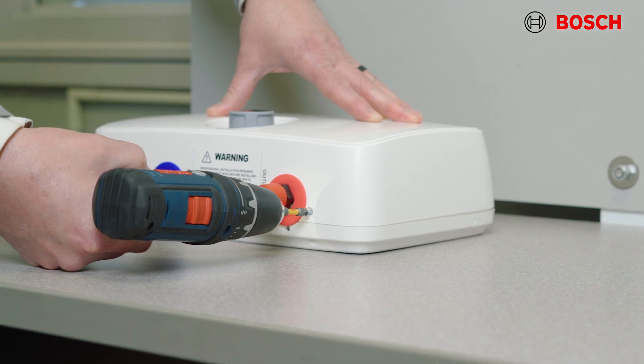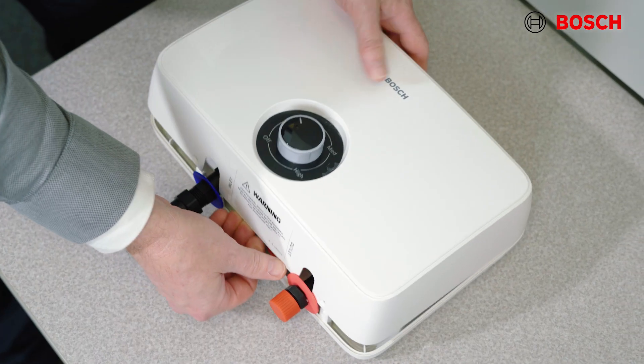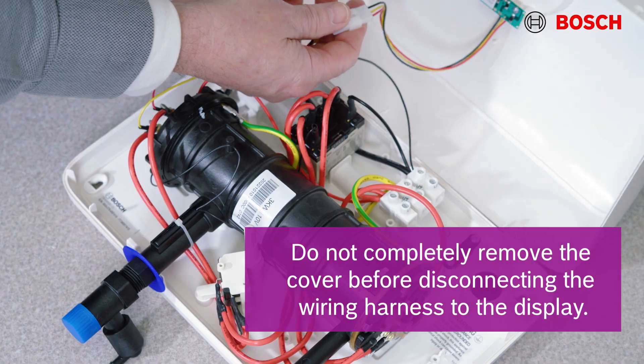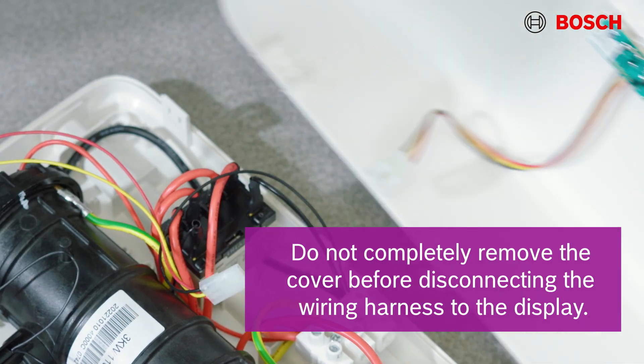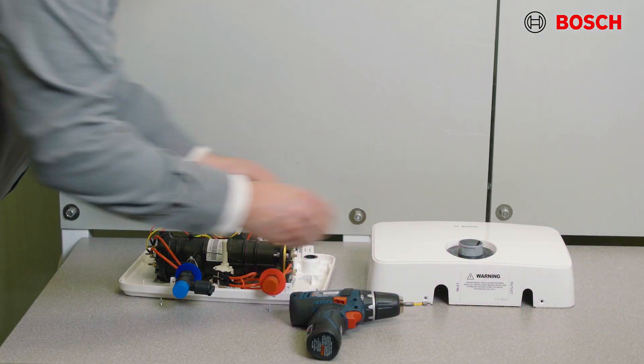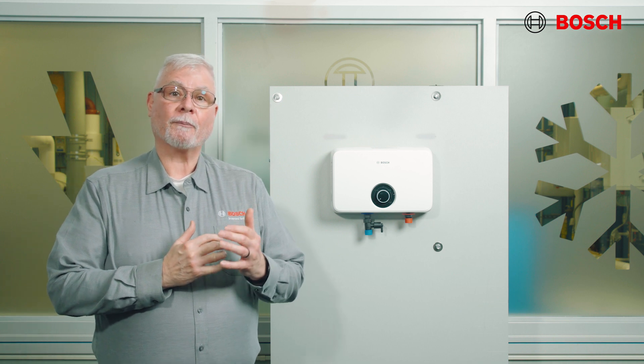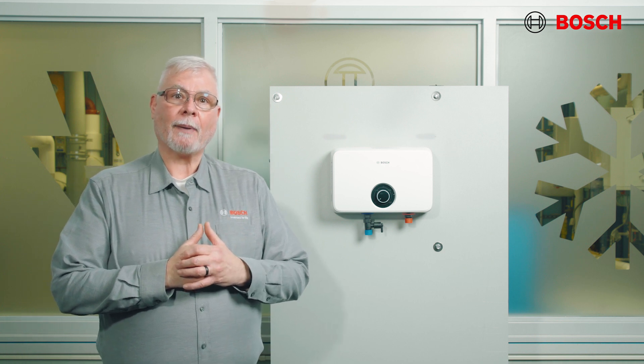To remove the cover, take the two screws off of the bottom. With the screws out, pull the bottom of the cover outward and swing it up, then lift away the tabs from the top. At this point you should be able to disconnect the wiring harness to the display. Once disconnected, completely remove the cover. You now want to bring your power into the cabinet pass the electrical supply wires through the round wire knockout in the back of the unit.